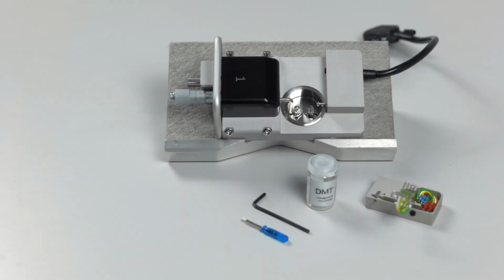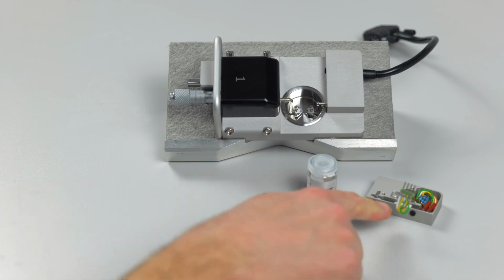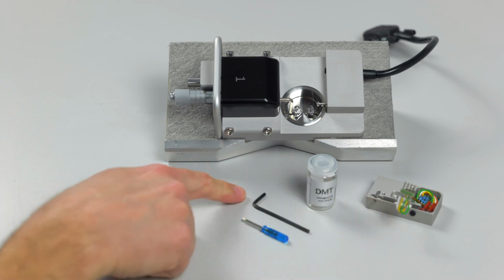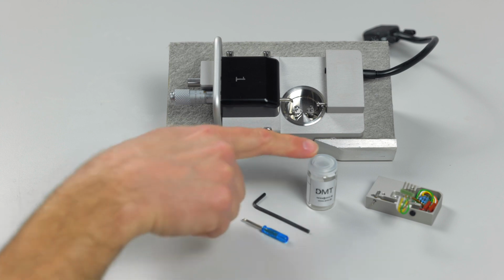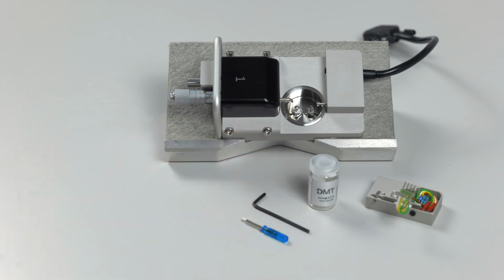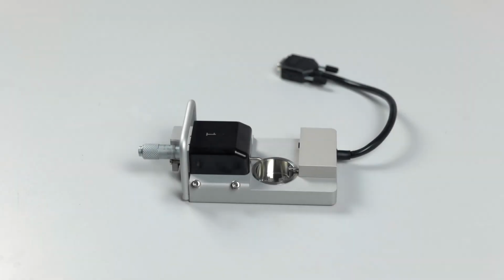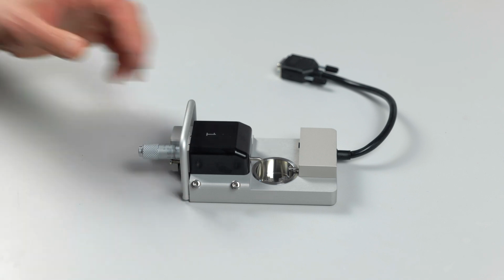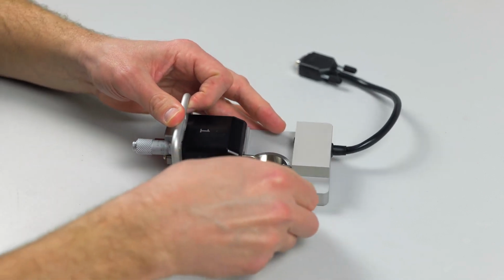In order to change an unresponsive force transducer in your 630 MA Myograph system, you will need a replacement transducer, your screwdriver and Allen key that came with the system, as well as the clear silicone grease. Before removing the transducer, the first thing we'll want to do is to remove the mounting support attached to the transducer pin.